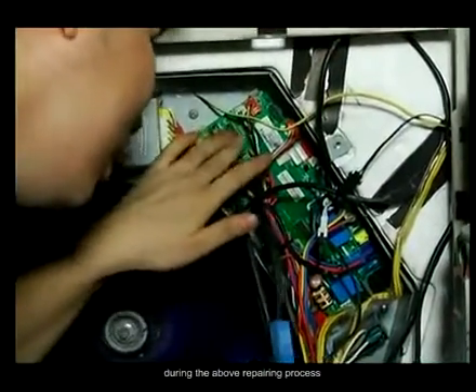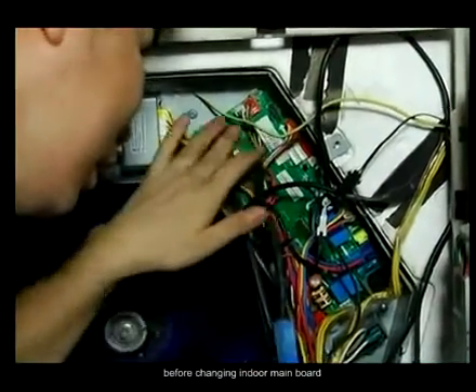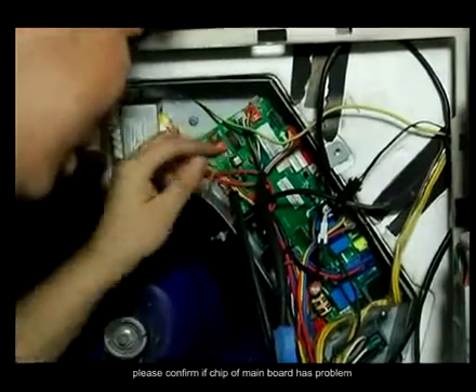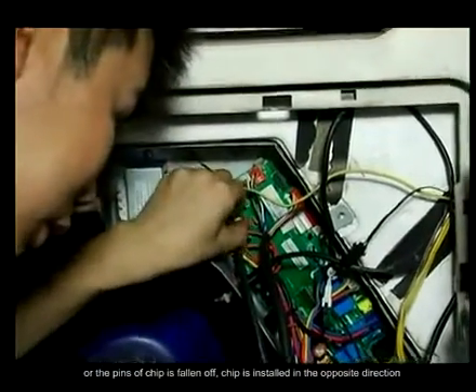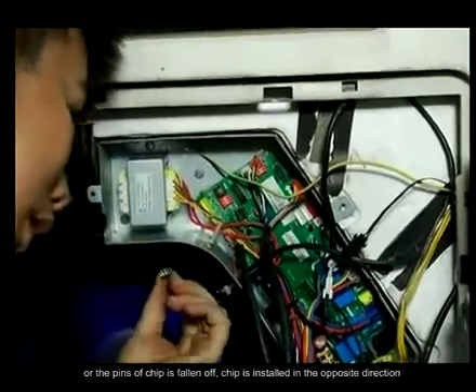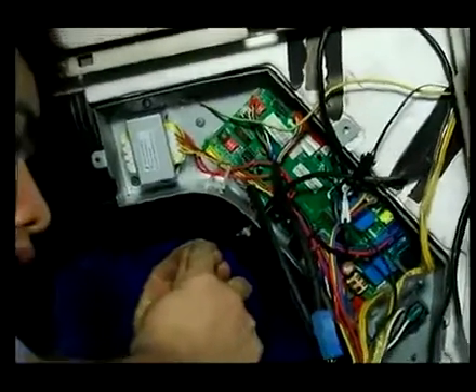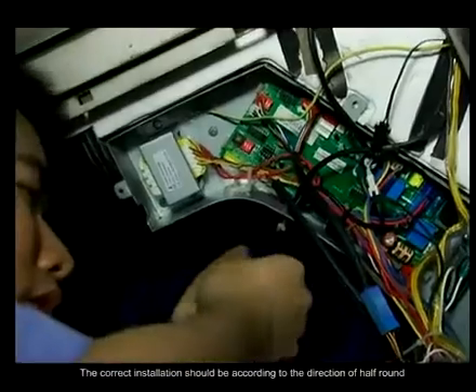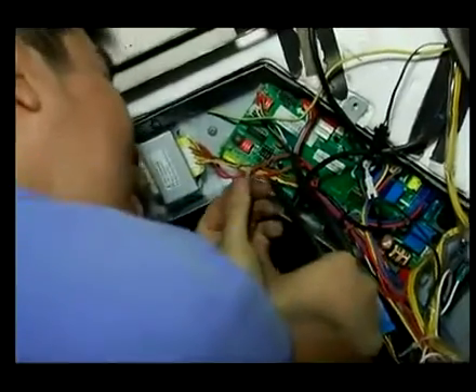During the above repairing process, before changing indoor main board, please confirm if the chip of main board has problem, or the pins of the chip have fallen off. Or the chip is installed in the opposite direction. The correct installation should be according to the direction of the half round.